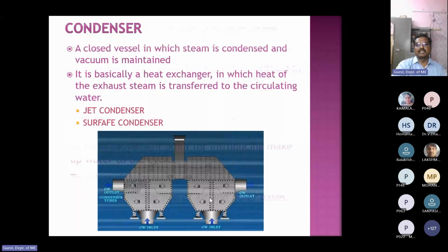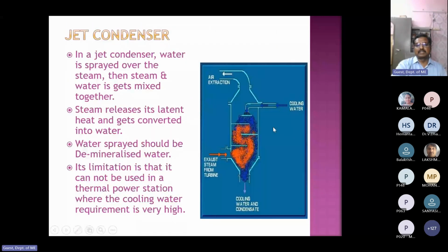This is a jet condenser. Steam exhaust is coming like this and going up. Cooling water is directly sprayed. These are called baffles, to slow down the process, mixing with the water. The main disadvantage of the jet condenser is we cannot reutilize this water, because if you want to reutilize it, we have to supply DM water here. DM water is demineralized water. We supply demineralized water only to the bottom. We cannot use normal clarified water.